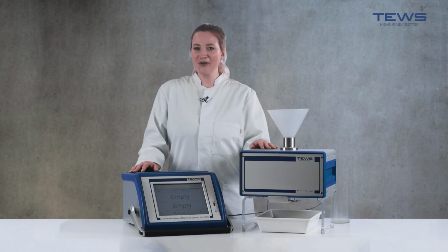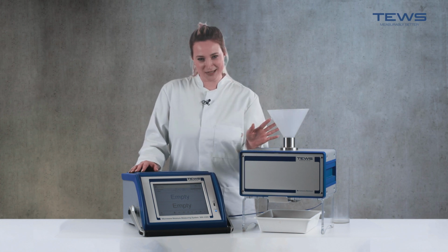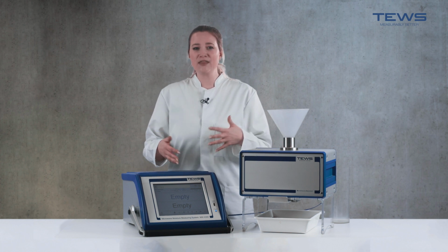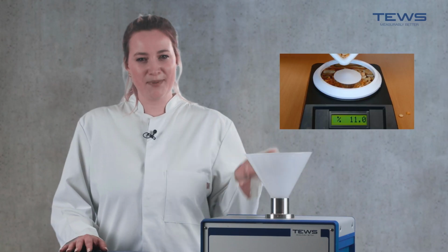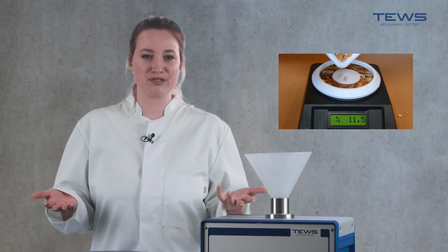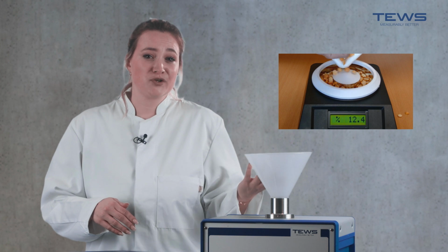Well, let's move on with the capacitive method. And don't worry, we're almost done here. Well, capacitive method works more or less in the following way. The higher capacity a product has, the higher moisture measurement result. Vice versa, the lower capacity it has, the drier the product, meaning the less moisture.